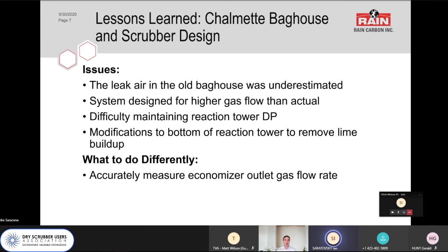Yeah, so we have a CEMS unit. So we actually have a flow meter put in all of our stacks. I think the problem was while we knew the flow at the cold stack, we didn't really know what the flow was at the inlet of the old baghouse before we had this system. So yeah, I definitely recommend, if you're going to install one of these things, accurately measure the flue gas coming into your baghouse at a wide variety of operational conditions, so you know pretty confidently what the flue gas flow is.